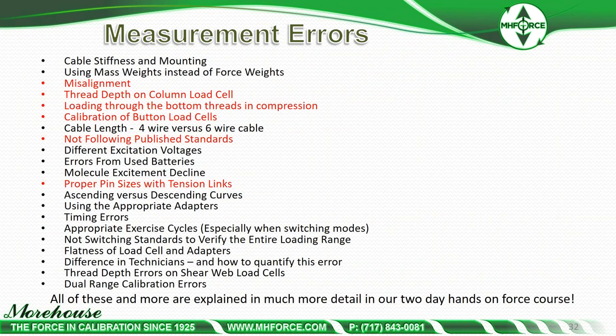Some measurement errors — the ones highlighted in red are the ones we talked about. We have two-day and five-day training courses where we discuss all the other errors: cable stiffness, mounting, using mass weights instead of force weights, different excitation voltages, errors from used batteries, molecule excitement decline, ascending versus descending, timing errors, and appropriate exercise cycles. Most of these are covered in our blog. Timing errors is the only one not yet in the blog — I presented that at ASTM.